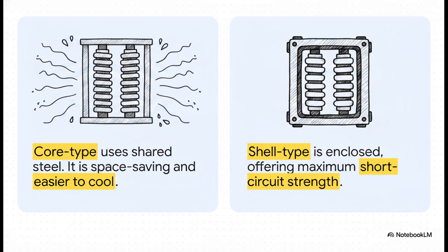While that core type completely dominates standard distribution and mid-sized transformers, because honestly it's just simpler to build, the shell type flips the script entirely. In a shell-type design, the core surrounds the windings on all sides. It completely encloses them, almost like a protective shell. This gives you superior mechanical bracing and the absolute maximum short-circuit strength required to withstand the violent physical forces inside those massive critical grid units.